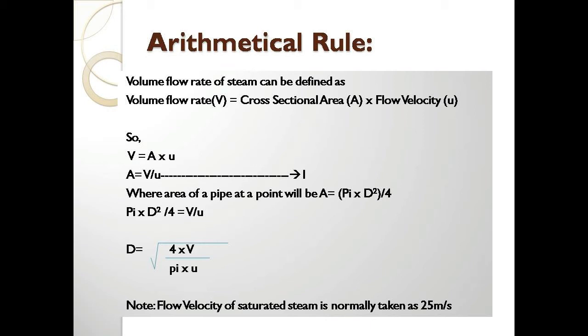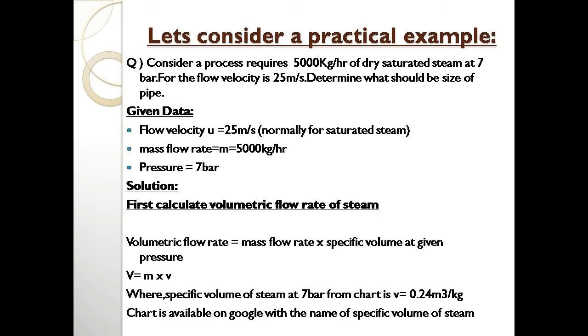The velocity range for saturated steam is from 25 to 40 meters per second, but we normally take 25 m/s for dry saturated steam. Now let's consider a practical example: a process requires 5000 kg per hour of dry saturated steam at 7 bar, with a flow velocity of 25 m/s. Determine the required pipe size.